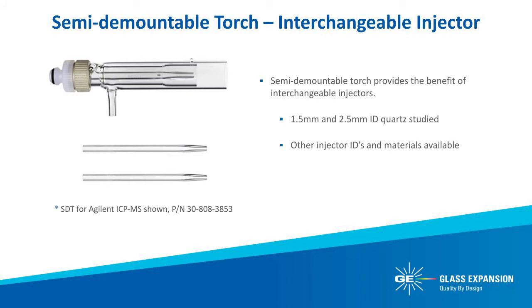Although a semi-demountable torch is not included with our single cell sample introduction system, it does provide an additional benefit of optimizing ICP-MS performance with interchangeable semi-demountable injectors using a single torch. In the final steps of our optimization report, we examine the benefits of using a 1.5 mm ID versus a 2.5 mm ID injector. Many ICP-MS instruments now ship with a semi-demountable torch as standard configuration. Glass Expansion manufactures many semi-demountable torch designs for instruments that do not have a standard semi-demountable torch option.